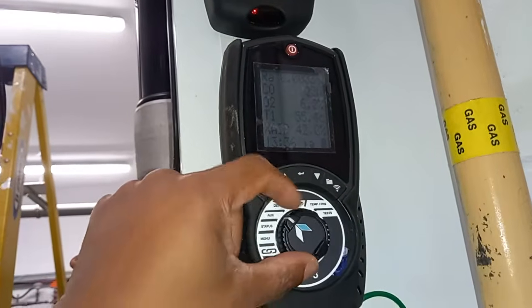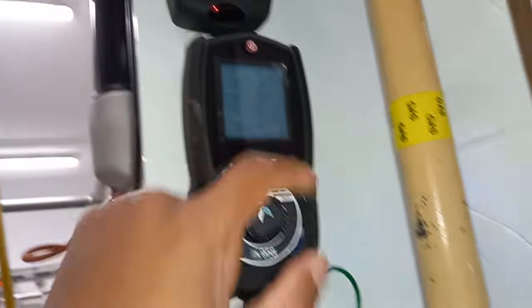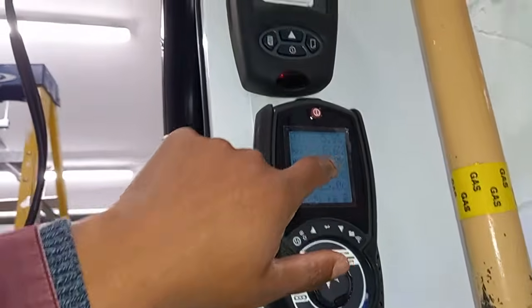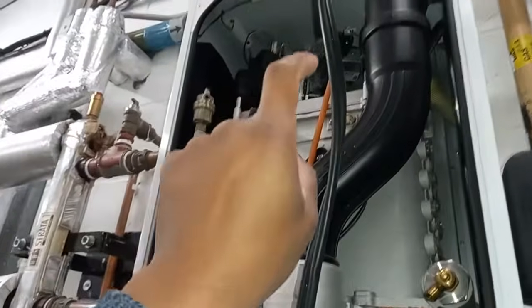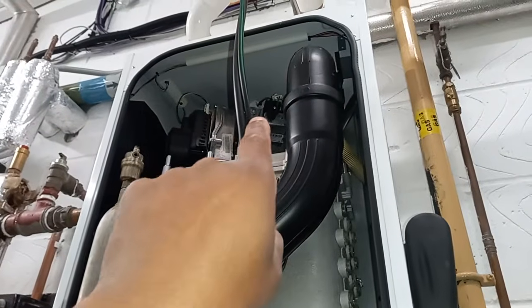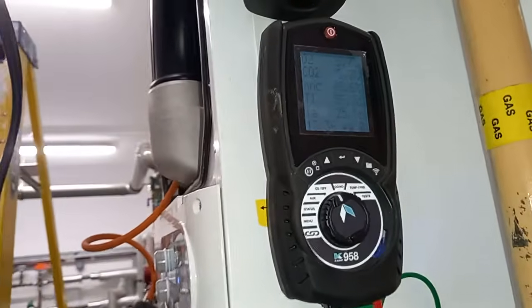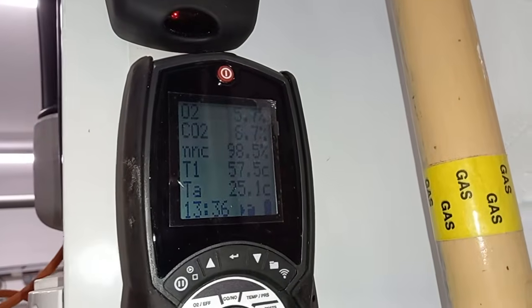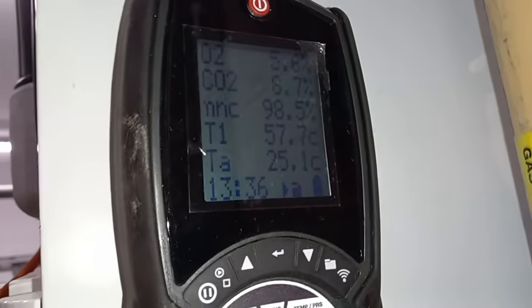I want to see my CO2, check inside the manufacturer's instructions what it should be. But I believe on this particular unit, you can't adjust the gas valve, or that it's not recommended, I believe, on this particular unit. So I'm going to look for my CO2, wait for my flue temperature to stabilize, and then I'm going to print it in high fire.